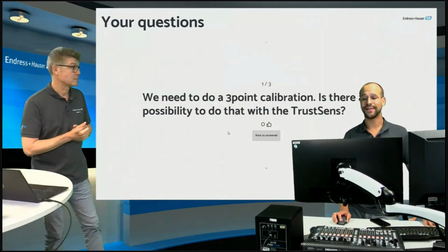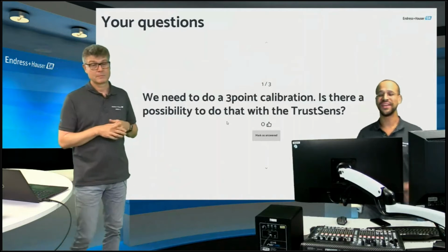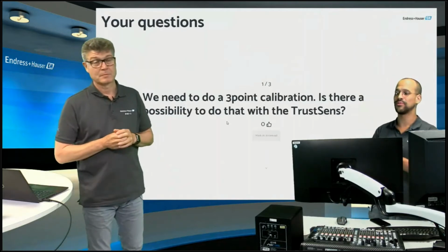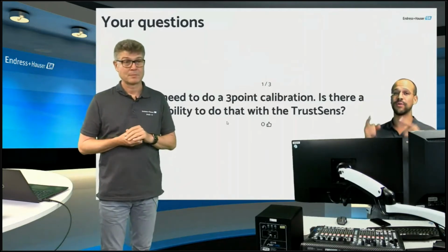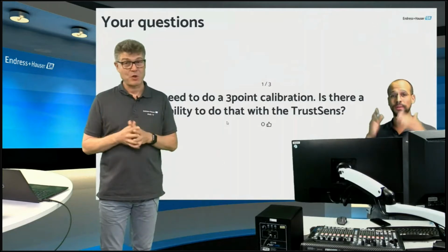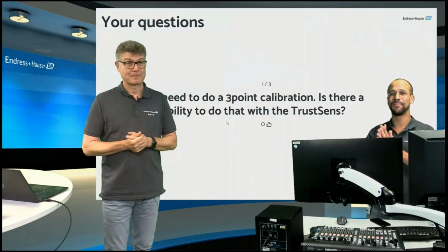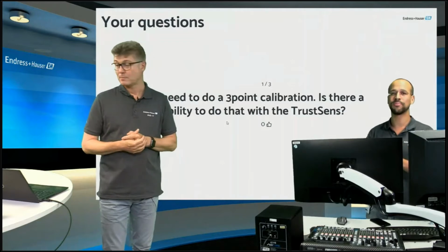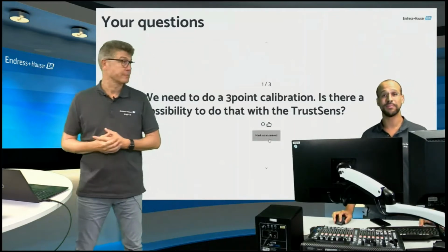All right, yeah, the classic one, we need a 3-point calibration. Is there a possibility to do that with the TrustSens? We will see that in the very end. Yeah. So we have a 1-point calibration. And of course, there's a difference to a 3-point calibration, but we will come to that from a mathematical point of view in the very end.